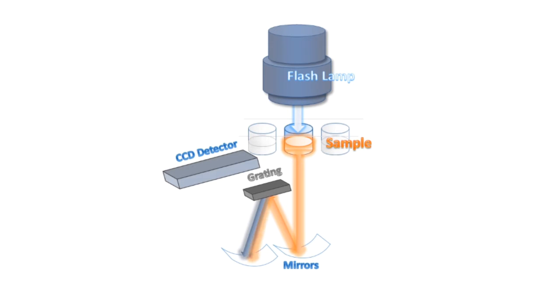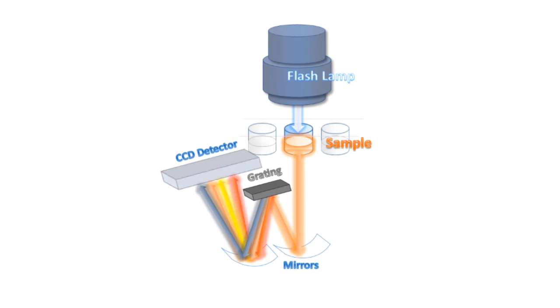The spectrograph mechanism firstly passes light through the sample. The beam is then focused and parallelized. The light is then reflected from a grating plate and diffracted into monochromatic beams with different wavelengths. Each of these beams propagates in a unique direction. They are then focused at different spatial locations along the CCD detector to produce values for the sample across the full spectrum.